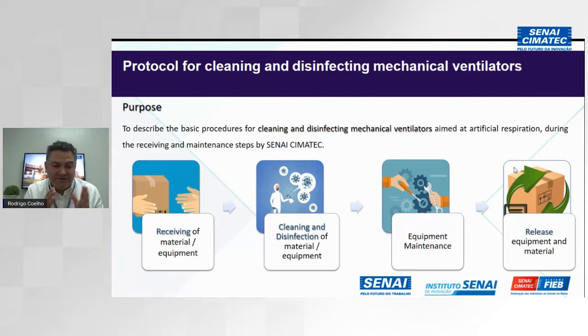So the first step, you can see here in this flow chart, is to receive the material and the equipment, where we need to disinfect and clean the whole box the equipment comes in. The second part is to clean and disinfect the equipment itself, which is inside. And then we have the whole maintenance procedure before we release the repaired machine back to the hospitals. So we will go into detail on all those steps in this flow chart, where we can check the main characteristics of each point. The first point is the receiving of the material and equipment.